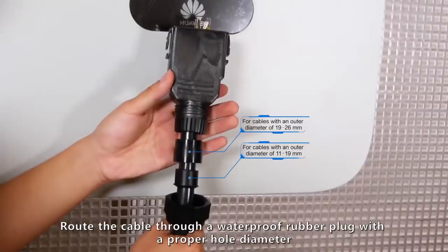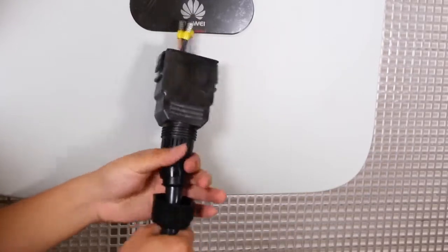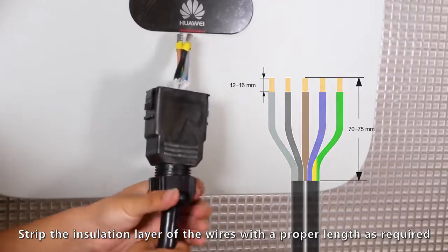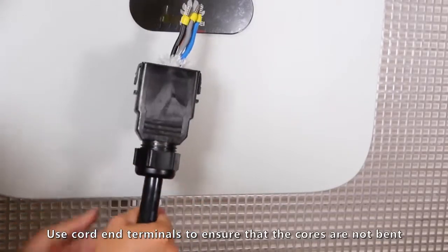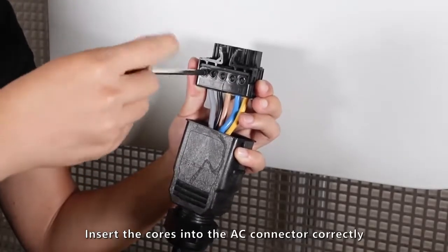Route the cable through a waterproof rubber plug with a proper hole diameter. Strip the insulation layer of the wires to a proper length as required. Use cord end terminals to ensure that the cores are not bent. Insert the cores into the AC connector correctly.